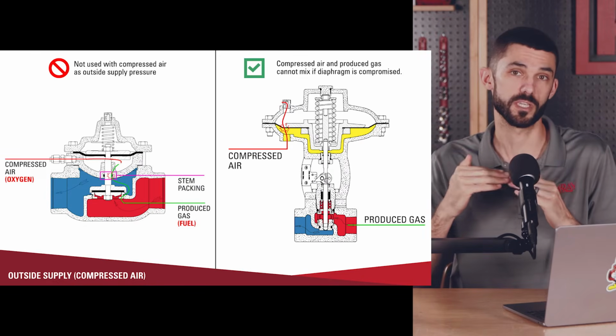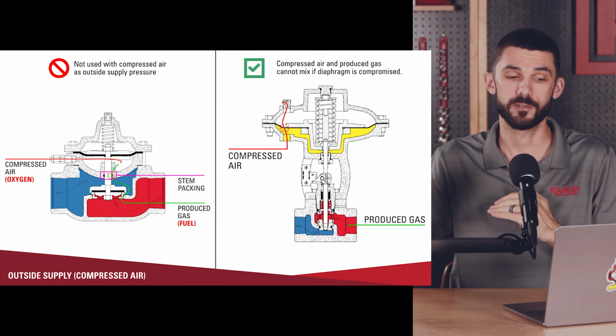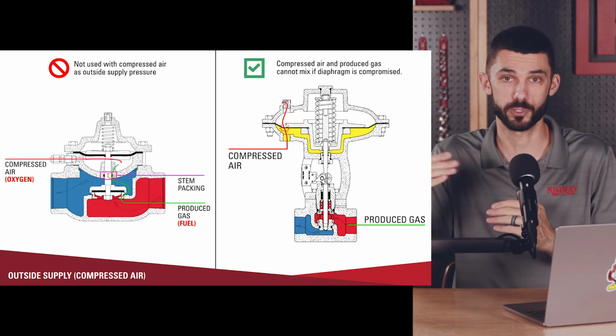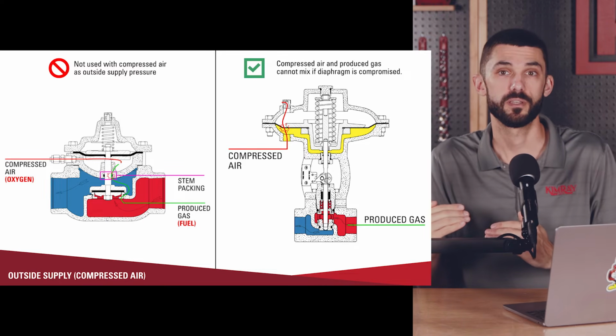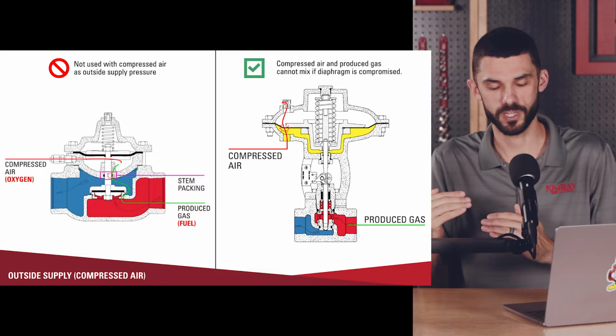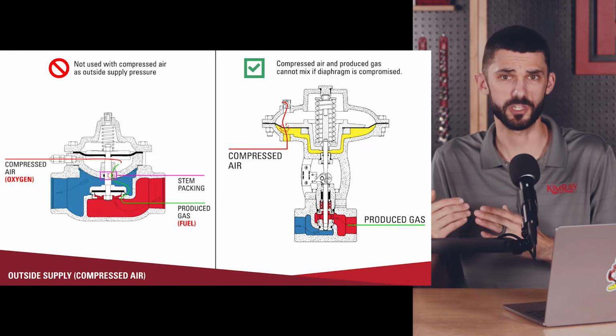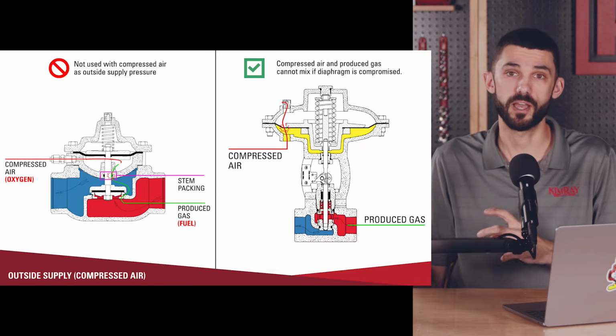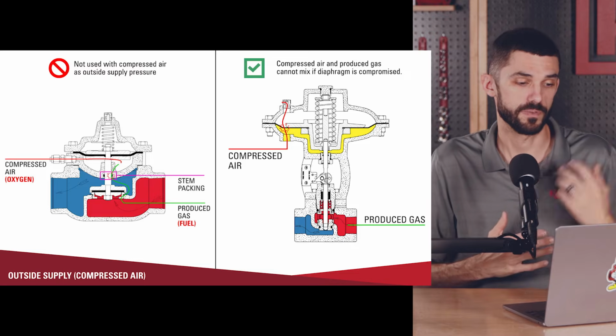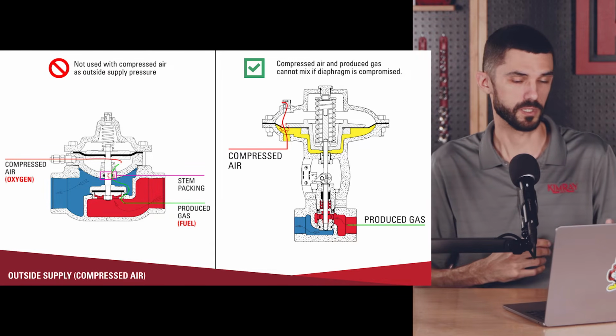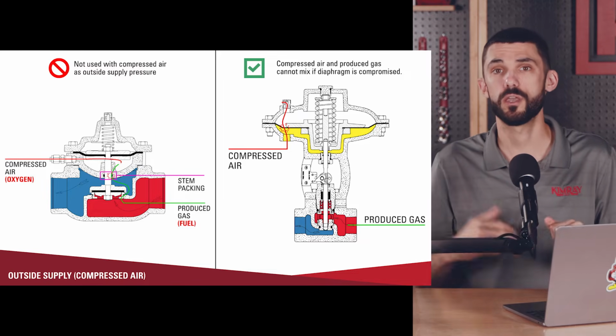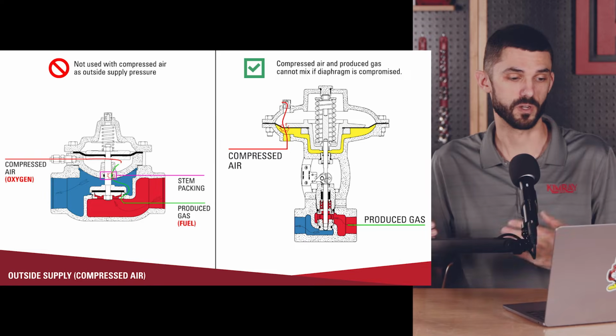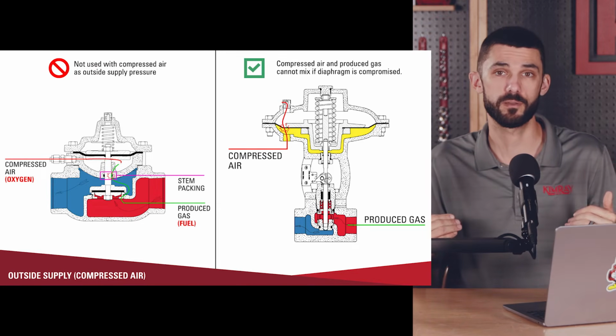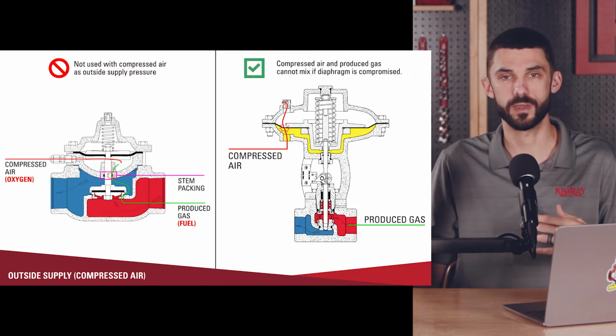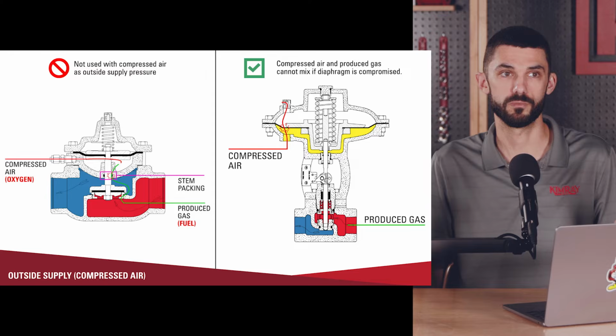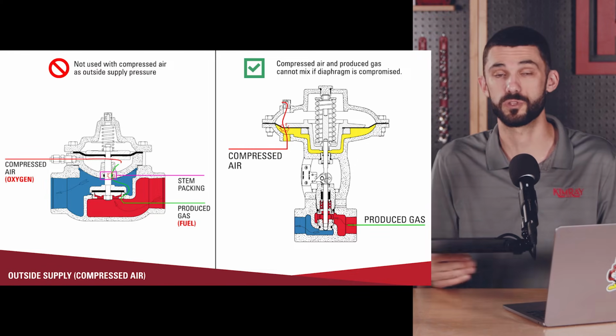The reason for that is because there is a single diaphragm separating the pneumatic supply coming from the temperature controller and the process flow. So if you were to have a failure of that diaphragm, there's a potential, if you were using compressed air, that you'd have fuel and air mix. But if you're using a high pressure control valve, typically a 1-inch control valve is what people use in this application, you can use compressed air because if there were a failure of the actuator diaphragm in that valve, that pneumatic signal is just venting to atmosphere, and there's no possibility of it mixing with your gas supply.